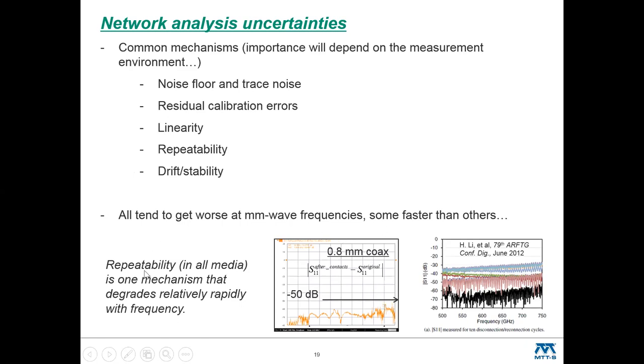A little example here on repeatability, just related to connectors, is shown in the bottom. The picture on the left is a reflection measurement using coax. This is a 0.8 millimeter connector, so up to 145 gigahertz. A device was measured, connected and disconnected 1,000 times, then measured again. The difference in dB terms, vector difference in dB terms, is plotted here, so somewhere in the 50s. That's a little bit worse than lower microwave frequencies - somewhere in the 40 gigahertz range you might be in the mid 60s, but numerically that's fairly common.